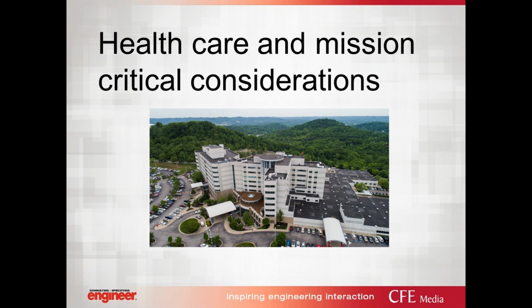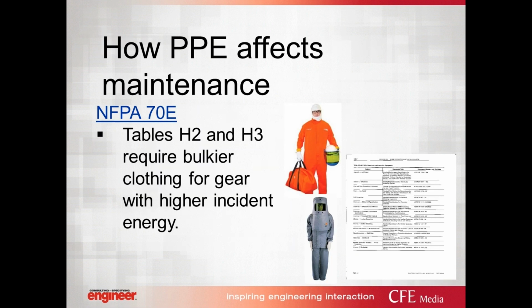Then we need to take a more holistic approach of what harm could happen if a main gear, whether it be the normal power supply system or the EPSS, were irreparably damaged. In the case of healthcare, this could cause diversion. It could cause loss of life in the case of any building. And also you could have to deal with the lawsuits and the repairs to the building that would go from there.